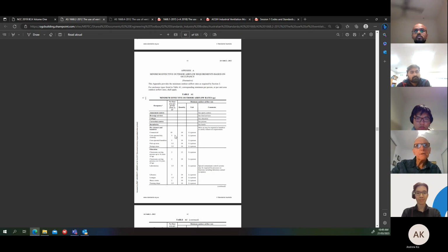If they don't, like a bar, for instance, if they say we're only allowed to have 100 people in the bar, but if you look at the table, it might say it's 1 person per square metre, and you might finish up with 300 people, which is like you were talking about before, Kaushik. Yeah, you want to have the right number of people, because your heat load's going to go up accordingly.